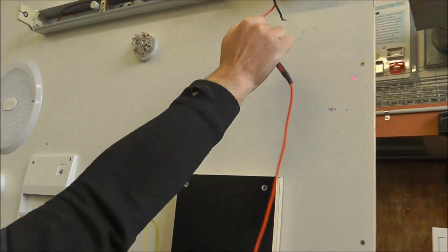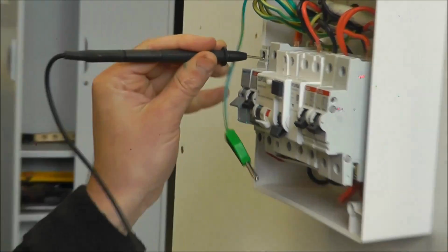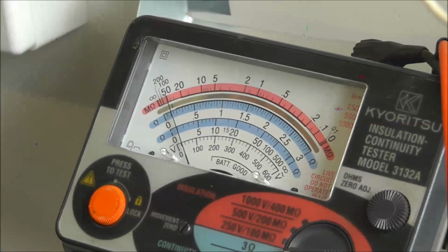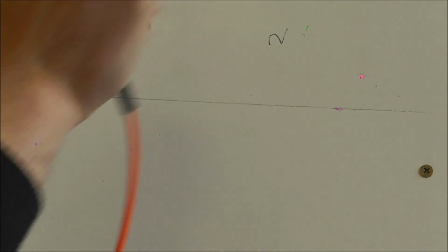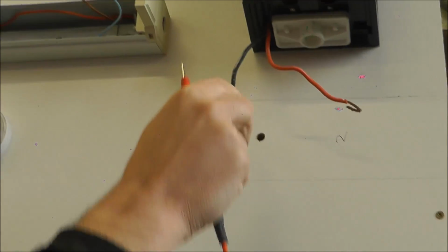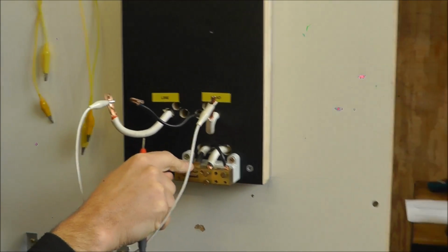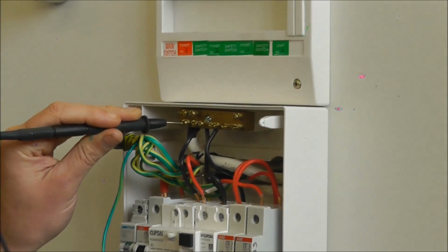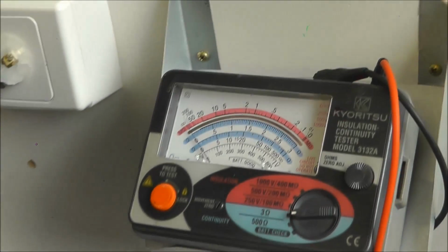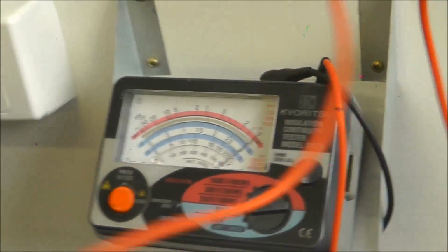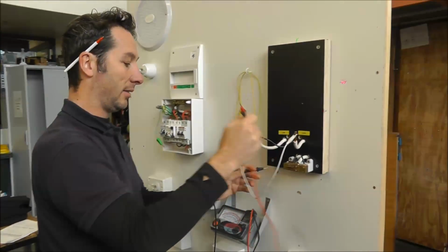My connection, Sam, goes from the active here to here, over to my main switch, and I've got a connection, it's good. The neutral, in case you're not a domestic guy, goes from here to here, out of here, over to the neutral bar. So I'm going to go from the neutral bar to the neutral, and it's good. So I write that down. In this case, it's like 0.01 and 0.01, whatever it is, pass and pass. Next test.